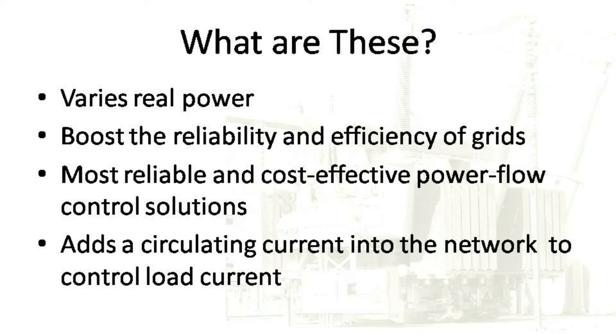The phase shifting transformer adds a circulating current into the network that either decreases the load current in the line where the phase shifting transformer is located, which is when they are operating in buck mode, or on the other hand, it could increase the load current when operating in what is called the boost mode.